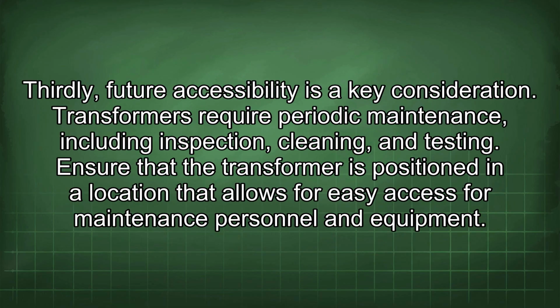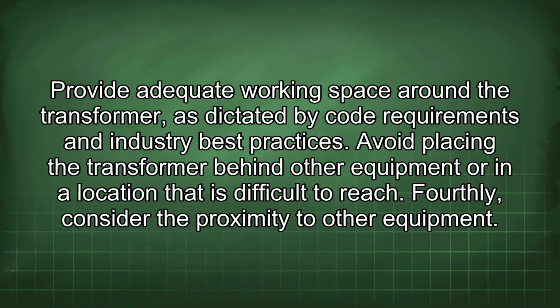Thirdly, future accessibility is a key consideration. Transformers require periodic maintenance, including inspection, cleaning, and testing. Ensure that the transformer is positioned in a location that allows for easy access for maintenance personnel and equipment. Provide adequate working space around the transformer, as dictated by code requirements and industry best practices. Avoid placing the transformer behind other equipment or in a location that is difficult to reach. Fourthly, consider the proximity to other equipment.